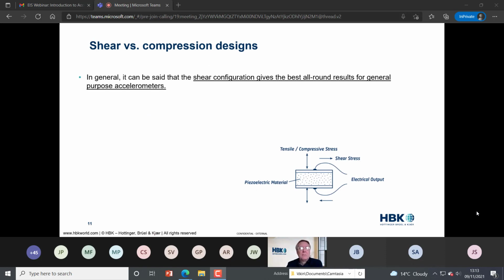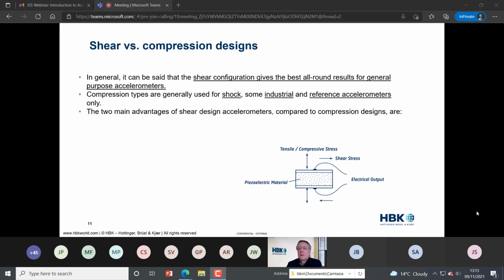Okay, so what are the relative benefits of shear versus compression? Well, generally, shear configuration piezoelectric accelerometers give the best overall results for general purpose measurements. Compression type accelerometers are used for things like high level shock measurement, ruggedized industrial accelerometers, and for reference accelerometers. And there are 2 key advantages that the shear design has over compression. And those are lower base strain sensitivity, I'll mention that a little bit more in a moment, and lower temperature transients. So with compression types, both of these effects can be troublesome if you're not aware of them.